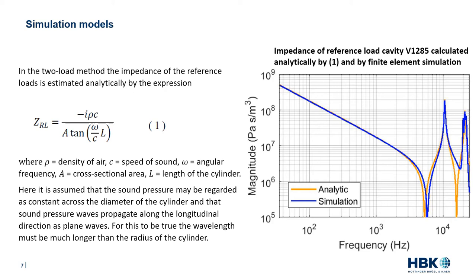In the two-load method, the impedance of the reference loads is estimated analytically by expression 1. It is assumed that the sound pressure may be regarded as constant across the diameter of the cylinder, that we excite and pick up through the full diameter, and that sound pressure waves propagate along the longitudinal direction as plane waves. In practice, especially when measuring on real ears, it's not possible to establish such ideal conditions. The graph to the right compares the impedance of reference load cavity 1285 cubic millimeters calculated analytically versus by finite element simulation from a 3D model of the exact geometry, showing a large difference especially at the minima — both in frequency and amplitude.